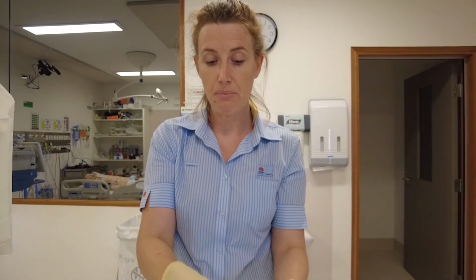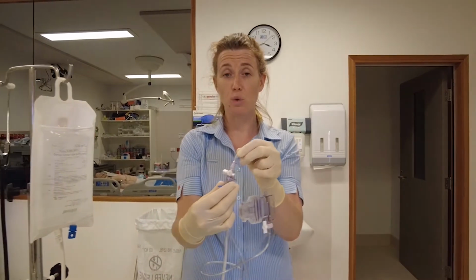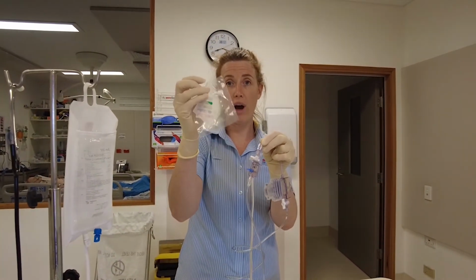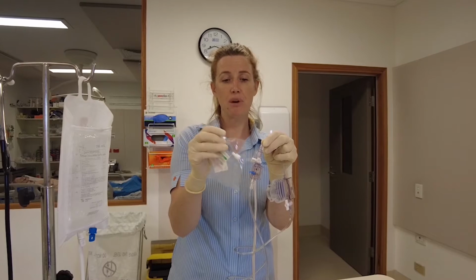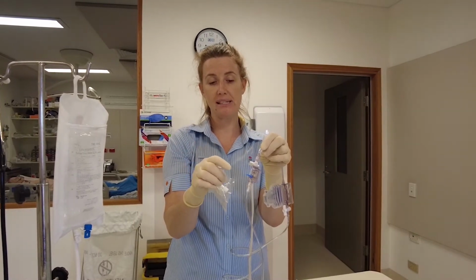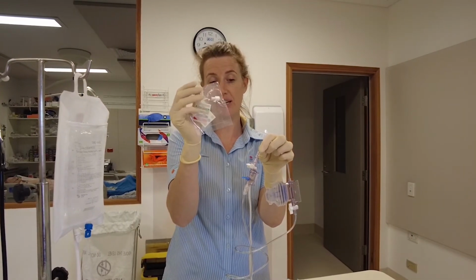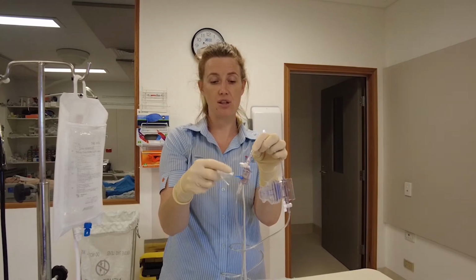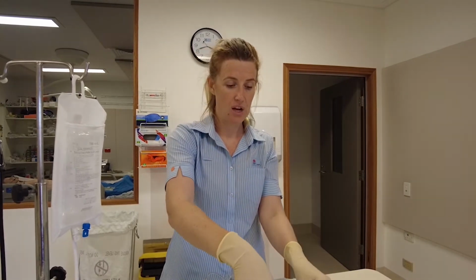So when you're setting it up, you need to change that cap to a non-vented cap, and there's a white one that comes in the pack. If for some reason you've come across an arterial line that's already been set up and it still has the vented cap and there's no white cap, use a red one. So use the red caps that you can find in the unit. I'm just going to do that now.